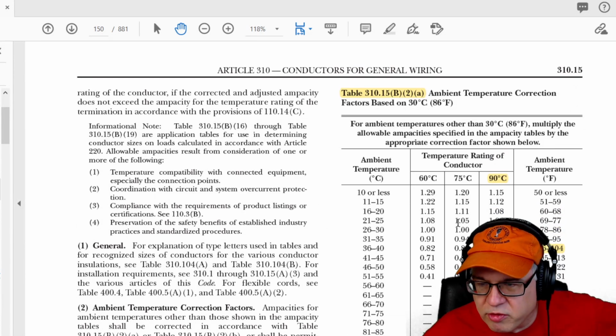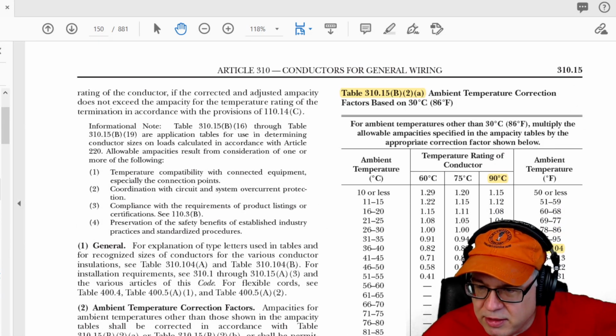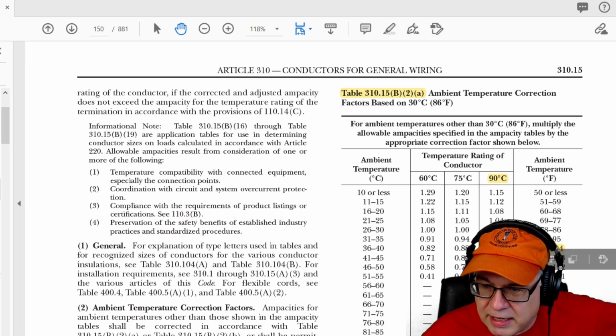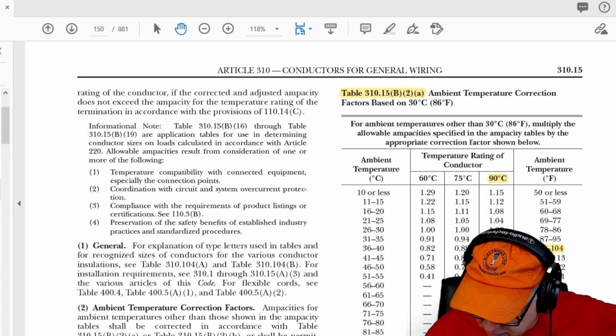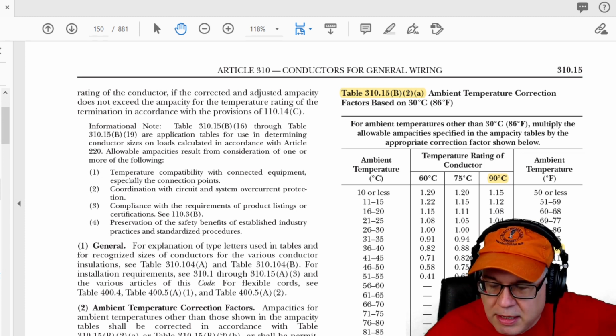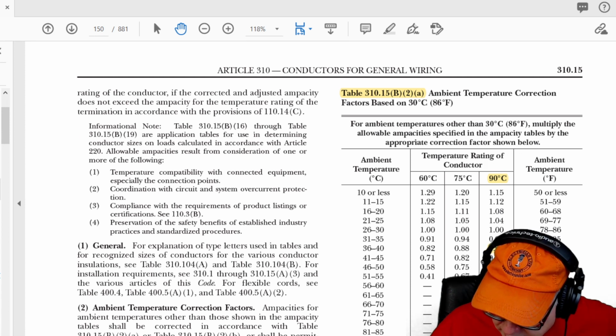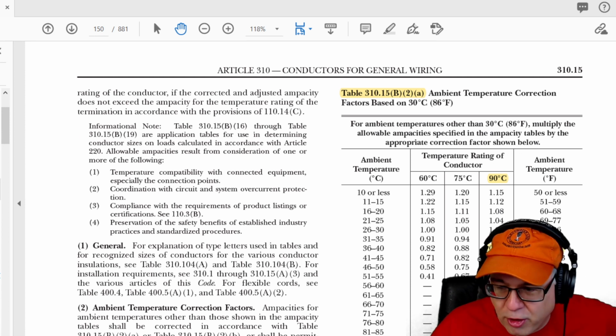All right, so it was 130 degrees Fahrenheit, I believe. The correction factor is 0.76 because it's supposed to be 90 degree rated insulation. But there's a reason I'm going to add the 0.41 down on my paper, because I'm going to worry whether or not this guy who wrote this question said NMB based on 60.